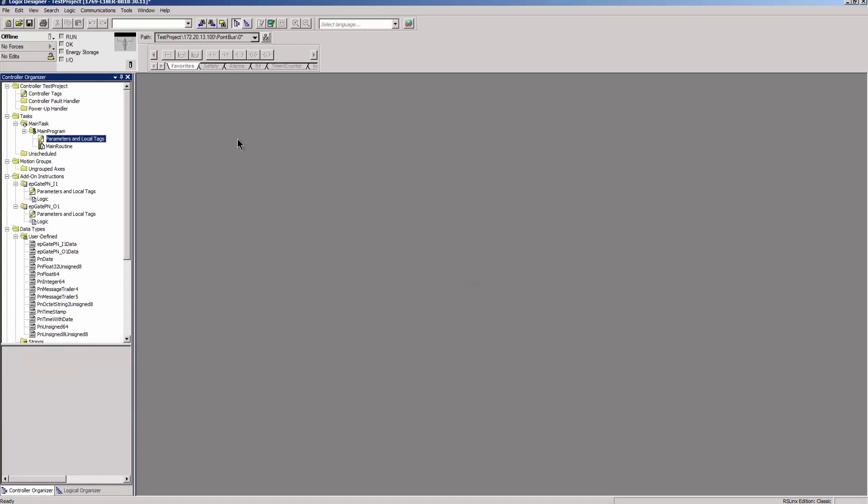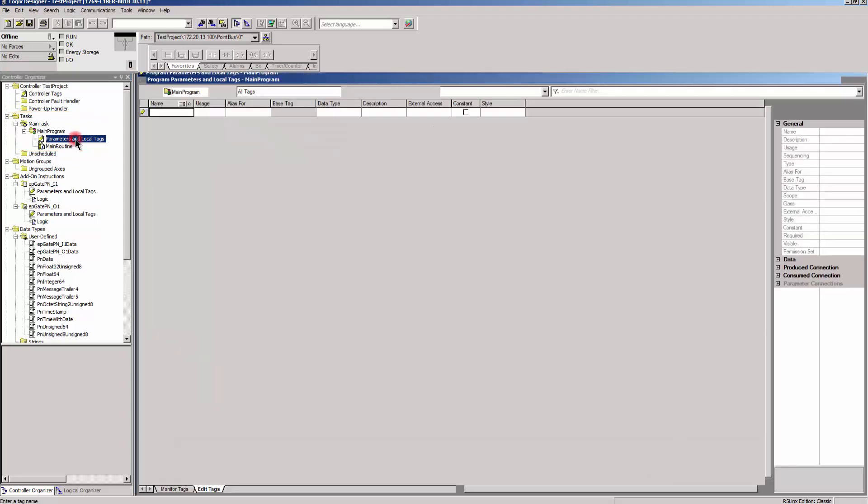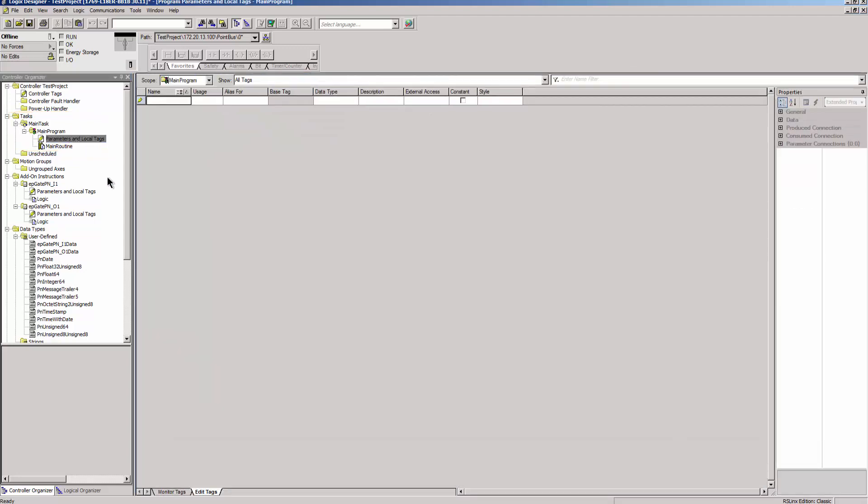After the AOIs have been imported successfully, the program tags can be created under Tasks, Main Task, Main Program, Parameters and Local Tags. In this example, we create one variable for the raw input data, one variable for the raw output data, and assign the input AOI and output AOI respectively.